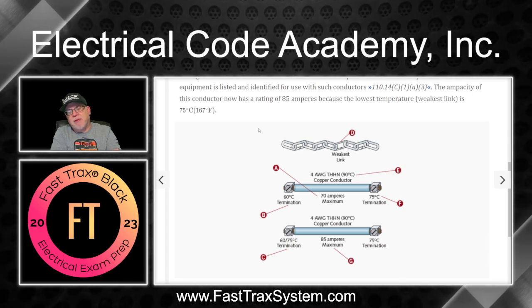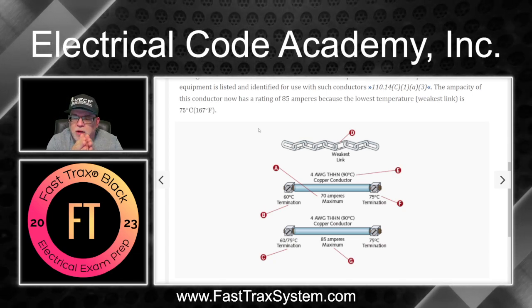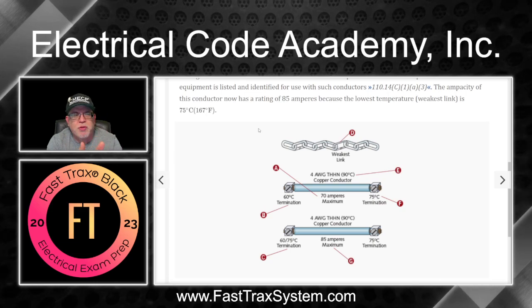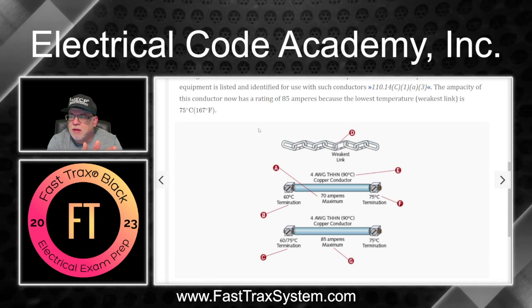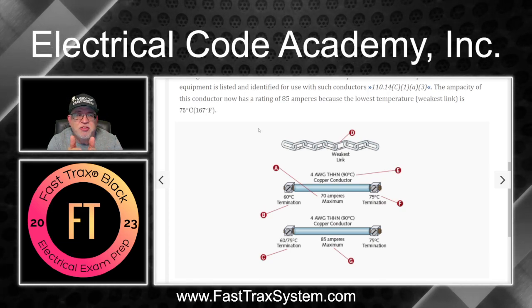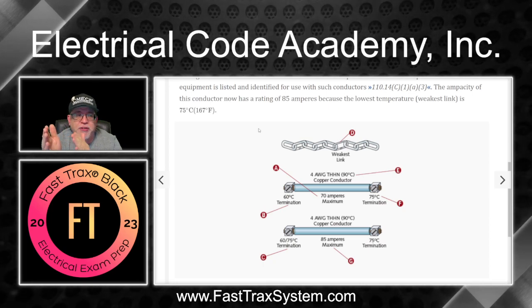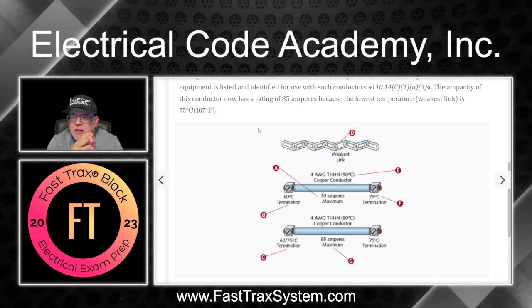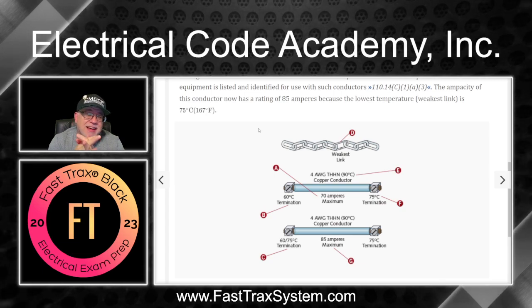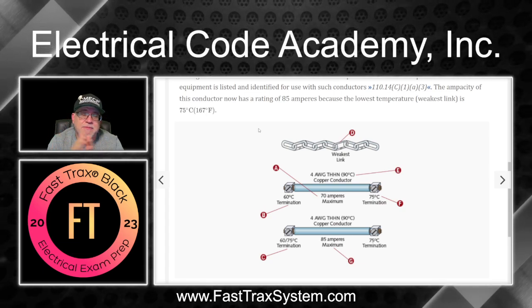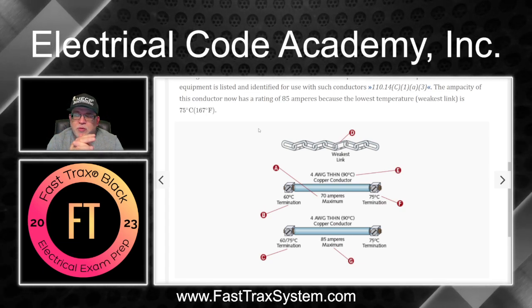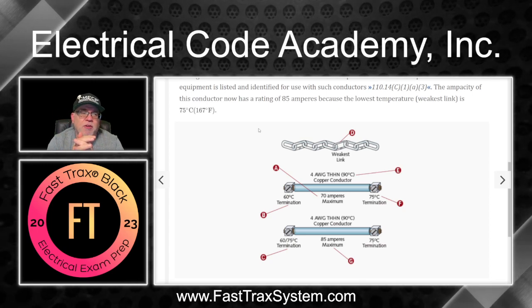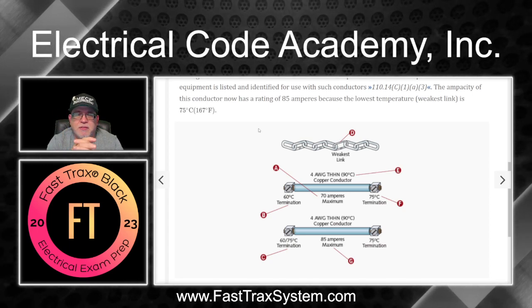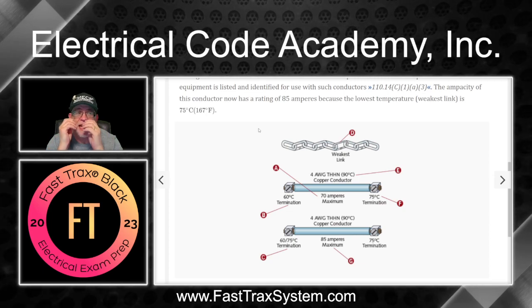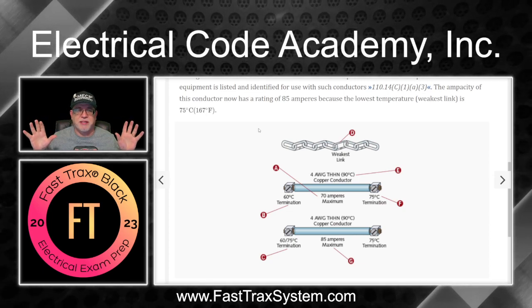And that's when you have to be able to explain to them that, well, wait a minute, if the terminals are rated 75, and the conductor's insulation is at least 75 or greater, in this case it's 90, then I can use the ampacity of the 75, okay? And this will sometimes cause quite a bit of arguments about, well, what is the ampacity of the conductor? Well, the ampacity of the conductor is the ampacity of the conductor without the termination limitations.